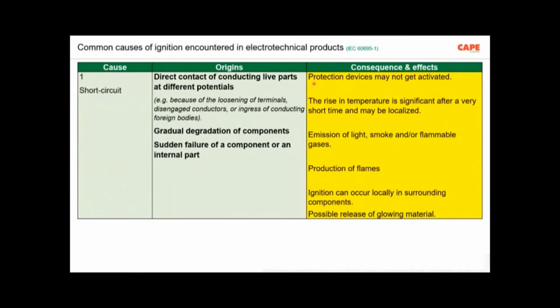The effect number one, always, the protection device may not get activated. The most important point is, in case of any abnormality, the protective device is supposed to operate within a certain time. In case of an overload or overcurrent, for example, the wiring and the MCB, the protective device, are selected in such a way that the conventional disconnection time and the conventional disconnection currents are what the whole system is able to withstand. So this we explained last time, but what I am explaining here is the protective device must get activated, and if the protective device fails to get activated, we will be in trouble.